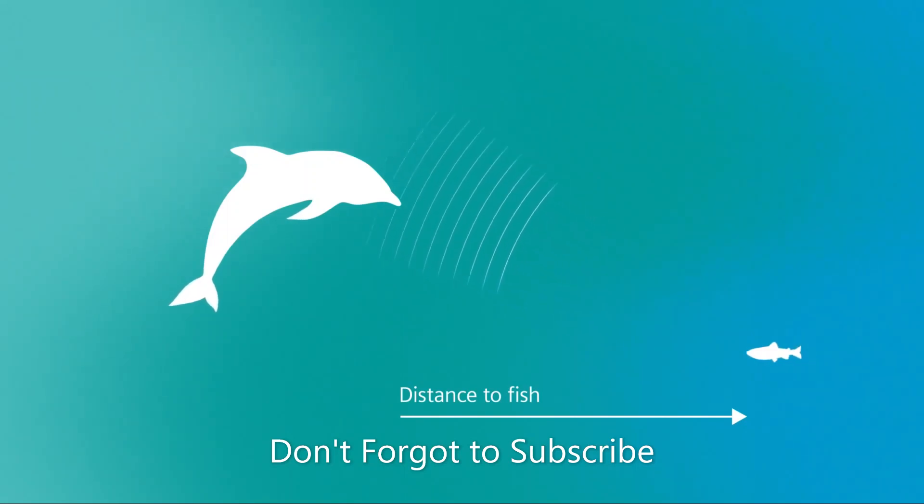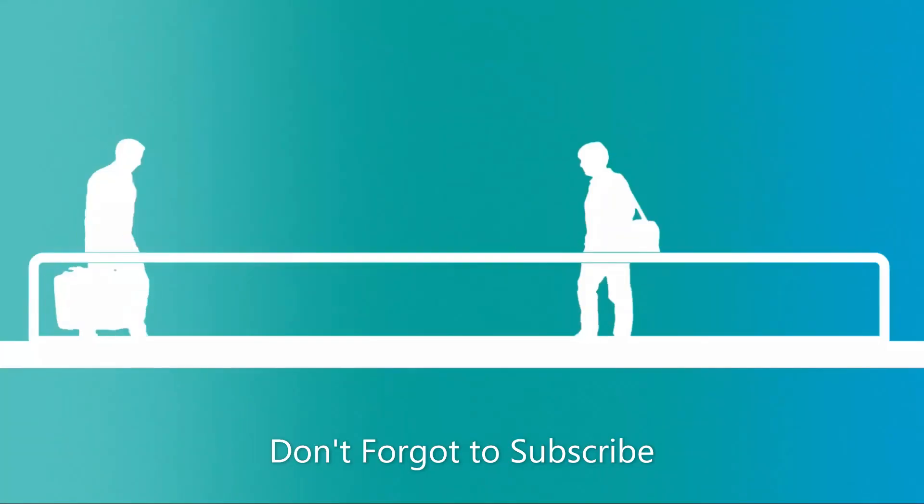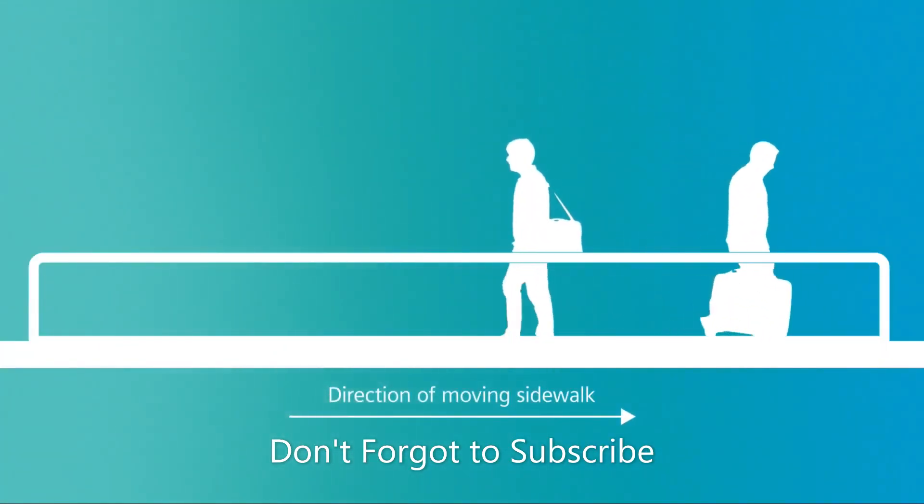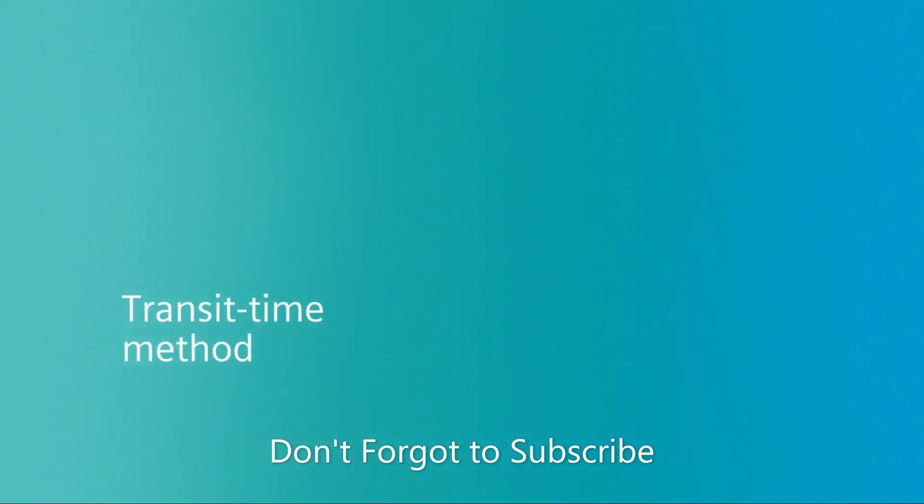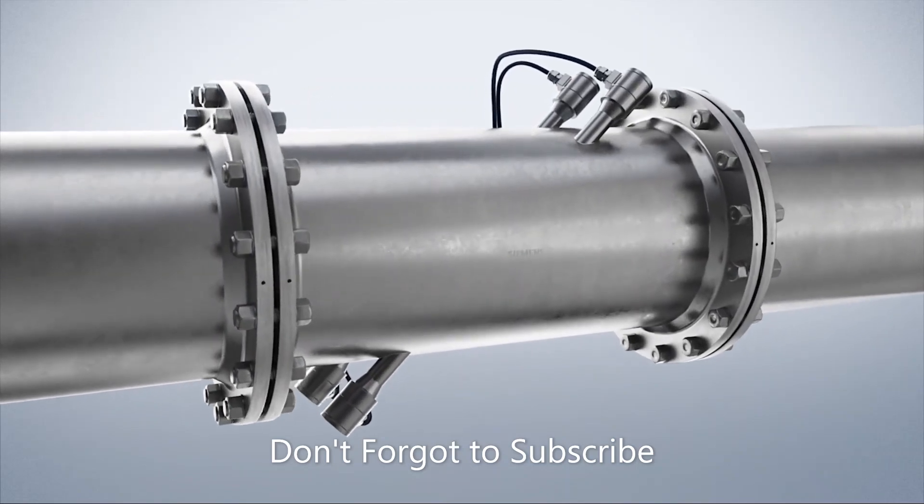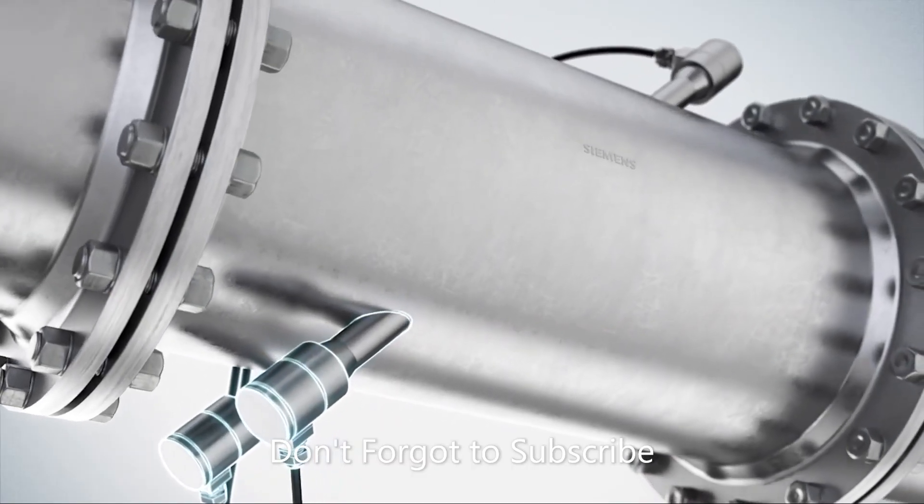Structure diagram of ultrasonic flow meter: Under both flow conditions, the upstream wave will flow at a lower rate than the downstream wave. As the liquid flows faster, the difference between the upstream and downstream times will increase. The flow rate is determined by the upstream and downstream times processed by the transmitter.